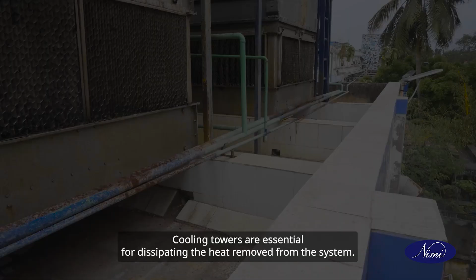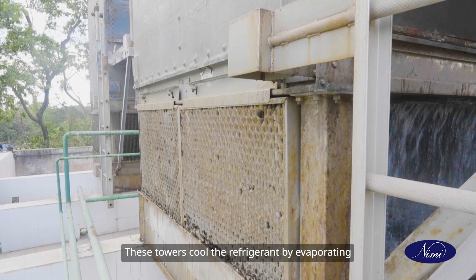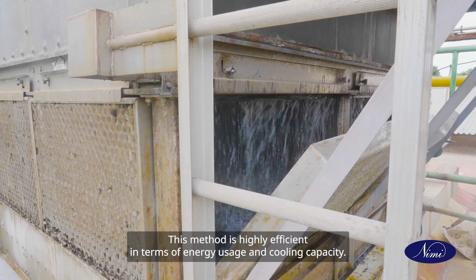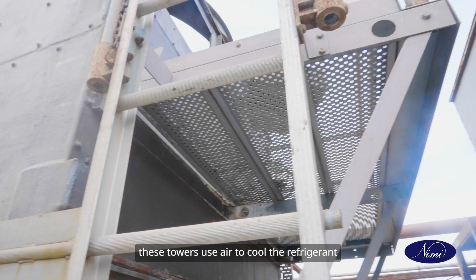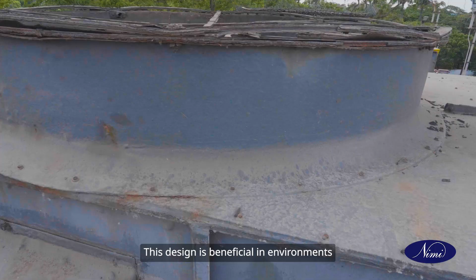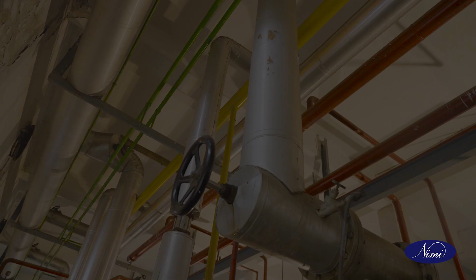Cooling tower. Cooling towers are essential for dissipating the heat removed from the system. Evaporative cooling towers. These towers cool the refrigerant by evaporating a small portion of the water, which removes heat from the remaining water. This method is highly efficient in terms of energy usage and cooling capacity. Closed circuit dry cooling towers. These towers use air to cool the refrigerant without direct contact between the cooling fluid and the air. This design is beneficial in environments where water conservation is important or where water quality is a concern.